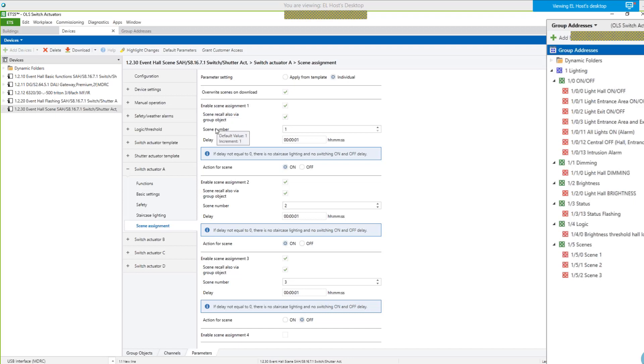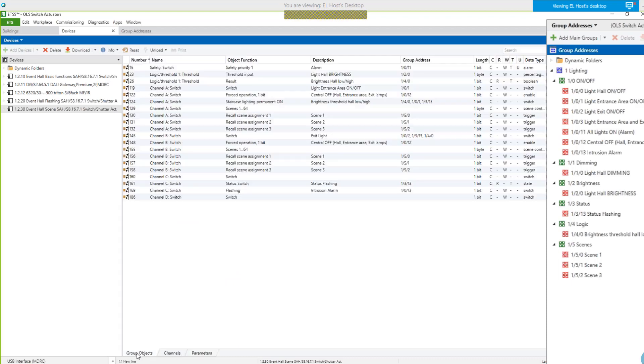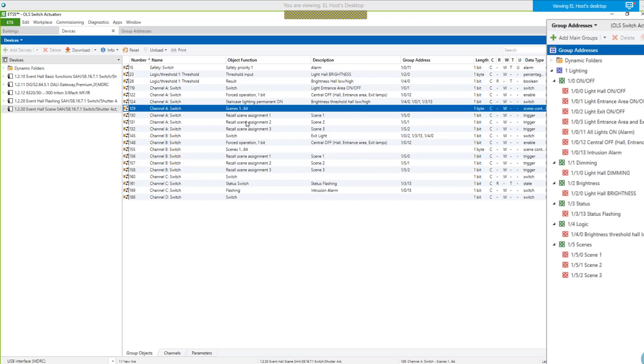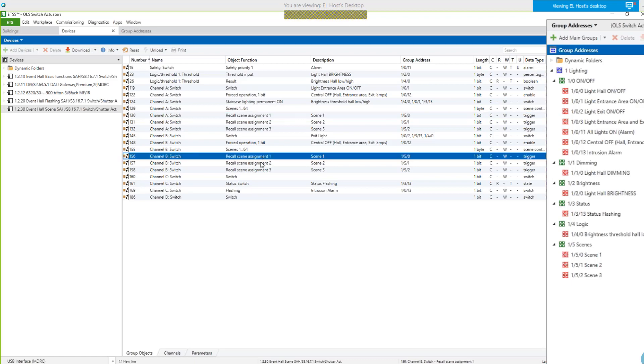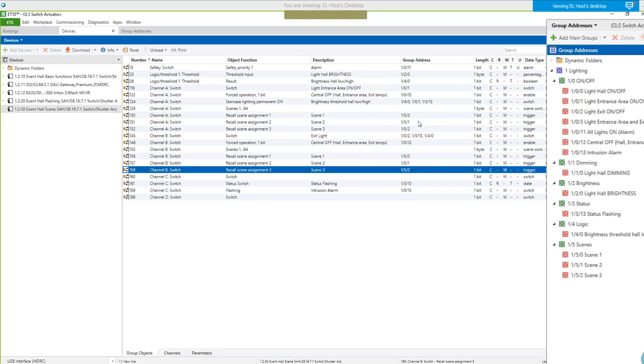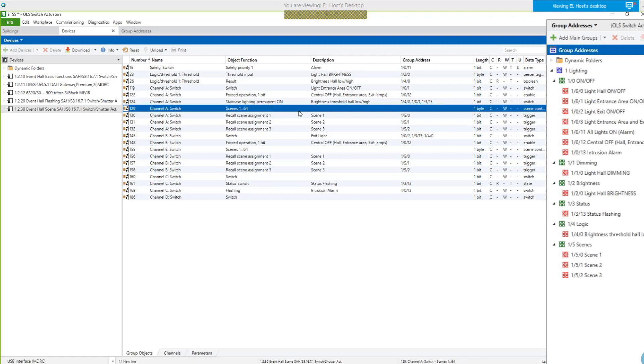You see here scene recall also via group object. If I enable this, then a one-bit object appears — not only the one-byte object, which is also available but not used here. I use only the individual group addresses or group objects appearing for recall scene assignment one, two, three for channel A, and the same for channel B. It's more group address assignment, but perhaps easier to use with a one-bit object for any push button or whatever you have.